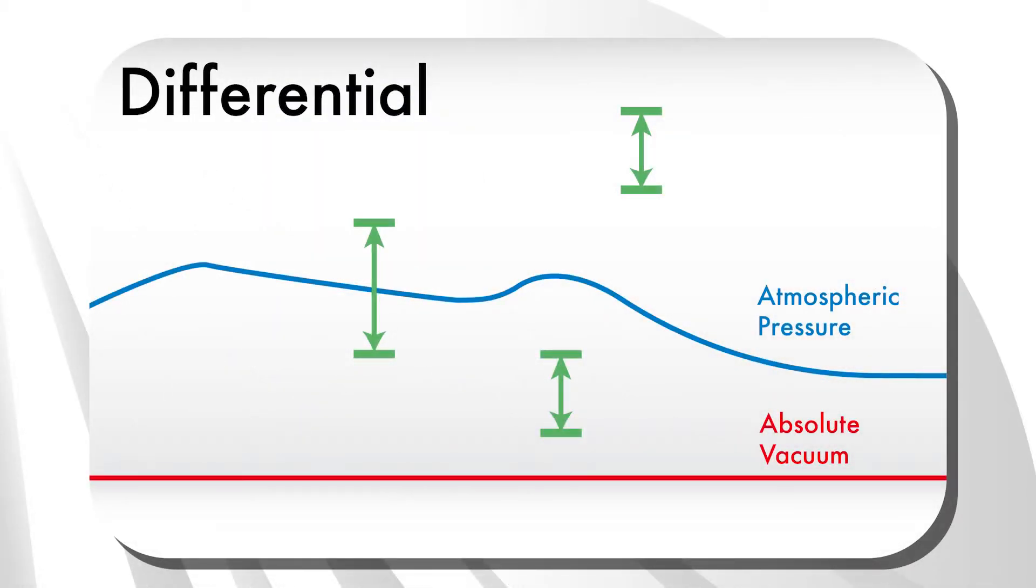Line or static pressure is the low pressure which the differential measurement is based. Differential pressure gauges or sensors typically do not allow for the static pressure to be above 50 psi, so there has been an industry need to perform accurate differential pressure measurement where high static pressure exists.